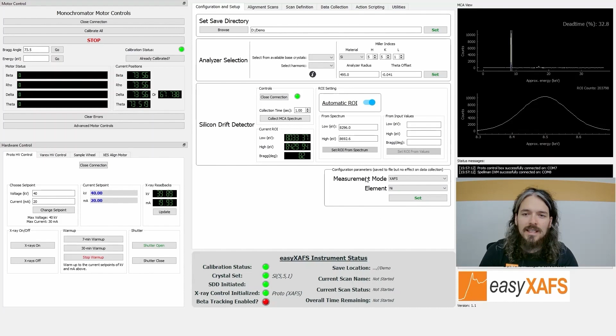For the scan definition, I'll give the sample a name. Here we're going to do a quick nickel foil check. Using the preset scans, I'll select the nickel K and the XANES check mode. You can see this is a single constant step zone. We'll scan the energy of the beam between these two energies, just with a coarse step size and a very short duration. This gives us a time per scan of just 20 seconds. This just gives us a chance to see that the sample is in the position that we expect and that we're properly capturing the absorption edge that we want to see.